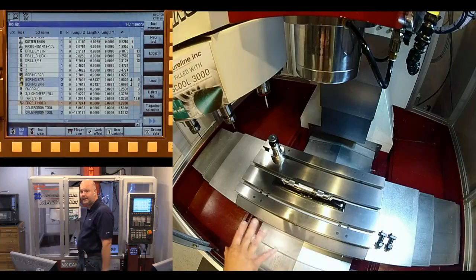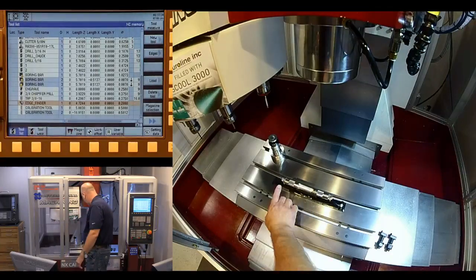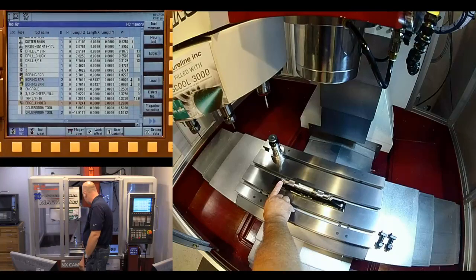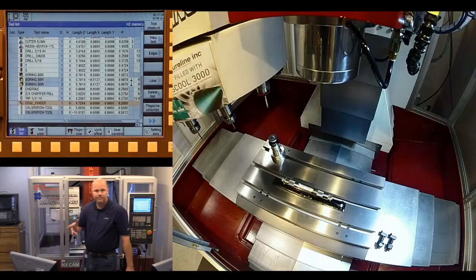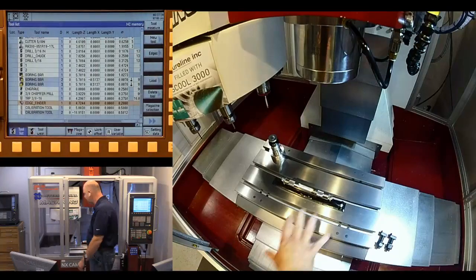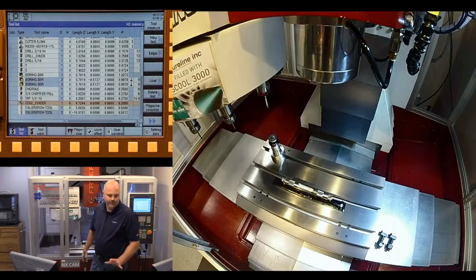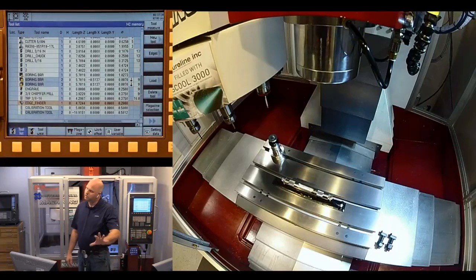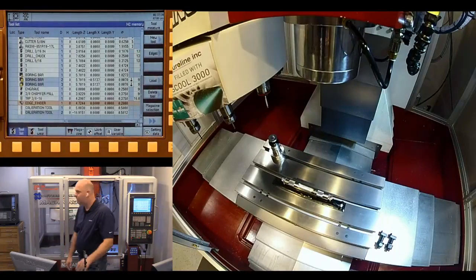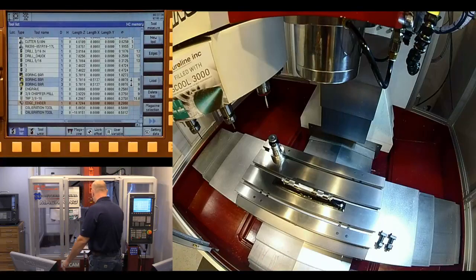You do want to let them settle out, because they do take a second to settle. But I can then, with this jam nut, move this level up or down just on the one side, and keep moving it back and forth, flipping it over and over until I get a nice consistent reading. Now my level is true. So don't start leveling things unless you know you have a true level. It's a very easy thing to check.